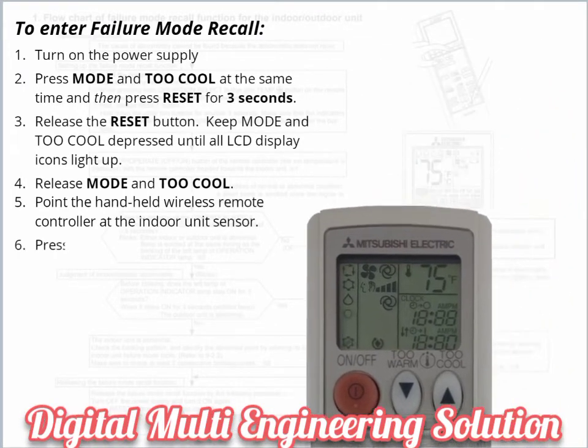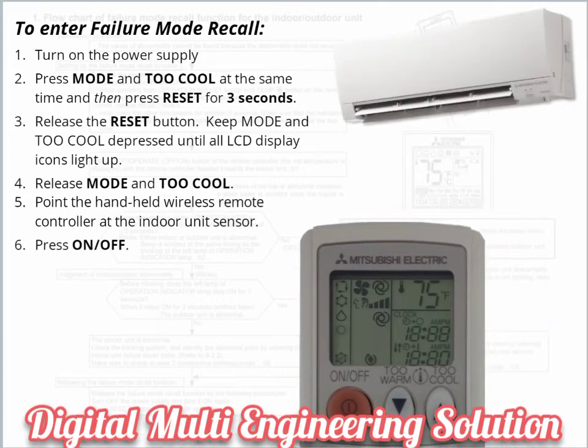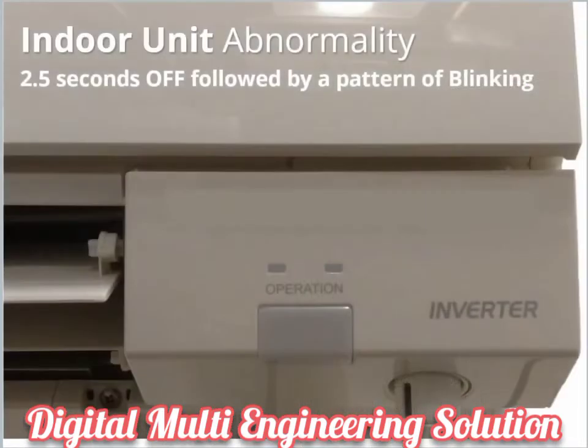Point the handheld wireless remote controller at the indoor unit sensor and press On/Off to send the Failure Mode Recall command. The green indoor unit operation light will display as confirmation. If an error has occurred at the indoor unit, the light will begin flashing and a beep will be heard at half-second intervals. It will then pause and repeat the sequence until action is taken.